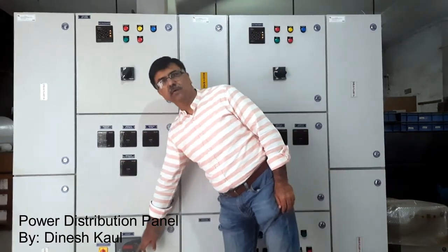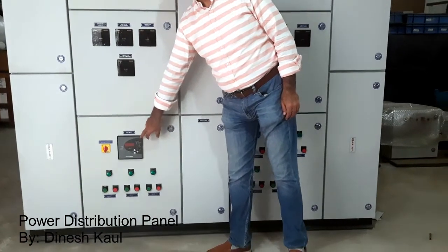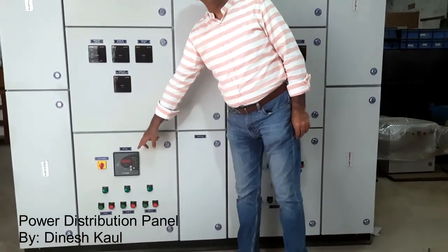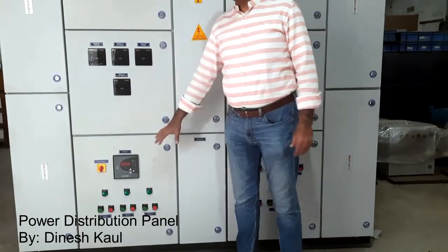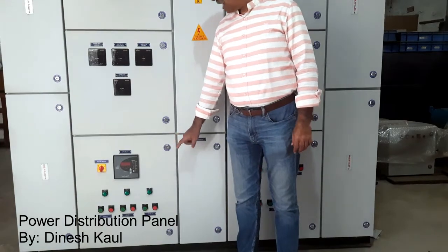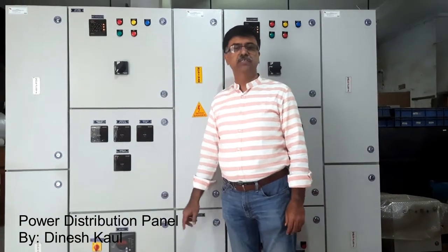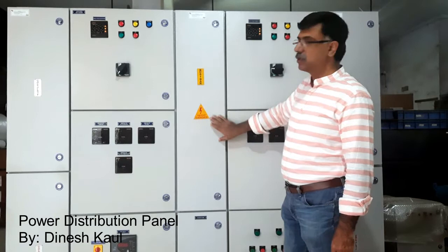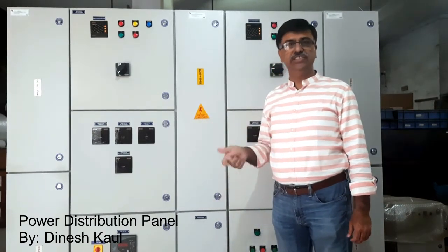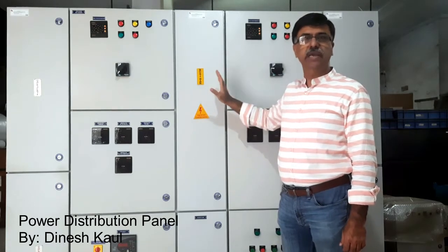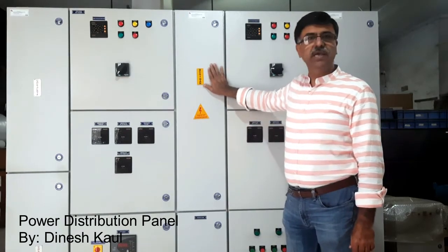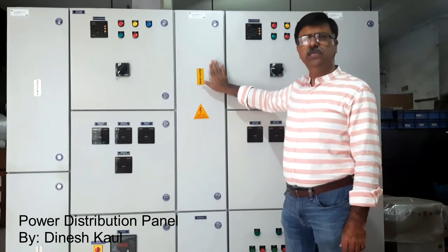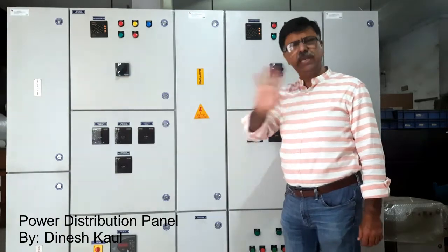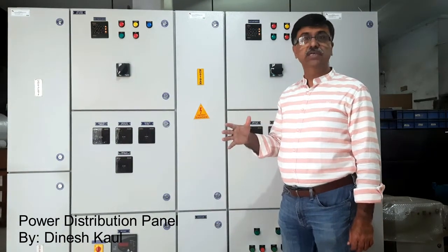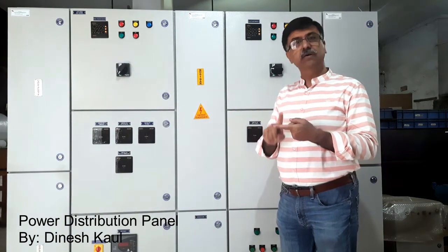Is it visible here? Can you see the power factor correction relay? Now this power factor correction relay will automatically correct the power factor, switching the capacitors on and off. However, in case the power factor relay is not working, you can still switch on the capacitors by push buttons. This enclosure is made out of 2 mm thick CRCA sheet and then powder coated to, let's say, about 80 micron. And the total design life of the system is about 15 to 20 years. But generally, you will not face any problem in this for the next 5-7 years, if the cabling is done correctly and if the termination is done correctly.